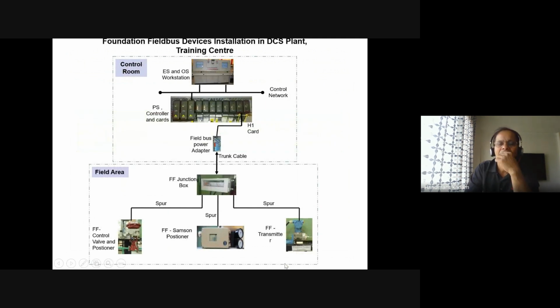So you can see here, this is the control foundation fieldbus, and as I told, this is another Samson positioner control wall, and these are FF transmitters - all these are FF field bus devices. This is a junction box, a field bus junction box, and the cable is named here as a spur cable. It is a slightly higher quality cable because it carries a digital signal and should not get interference from induced EMFs or RF signals. Therefore you have to take that care, and it is slightly more costly than normal cables. But in foundation field bus terminology, it is called a spur cable.